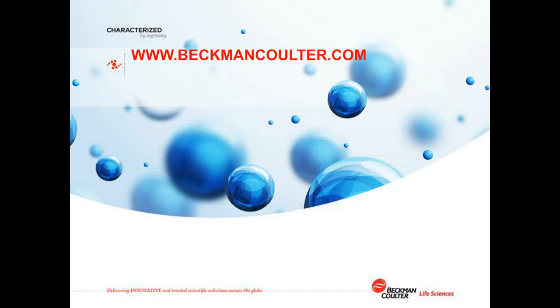And what can you do with old instruments that don't have a direct electronic records generation capability other than replacing the instrument altogether? Yeah, unfortunately, that is the only way forward. So if you've got an older instrument which just gives you a paper printout, generally speaking, there's not much you can do with it.